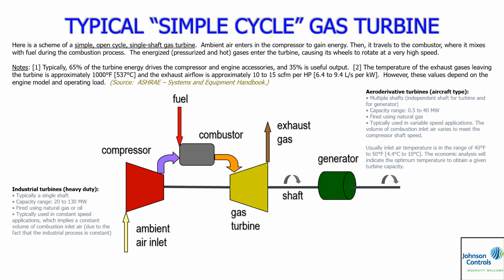So the bottom line, the natural gas, and these are usually variable speed applications. Now a couple of things with these. Usually the inlet air temperature is in the range of 40 to 50 degrees Fahrenheit. An economics analysis will usually indicate what your optimum temperature is. When the Bechtels of the world and the Kiewits of the world and Shell and ExxonMobil, when we're working with those guys, it's always a system analysis. What is the right temperature to get the inlet air to, and how much turbine capacity can we gain by making the temperature colder? And we'll get into that in just a minute. It's always an economics analysis.